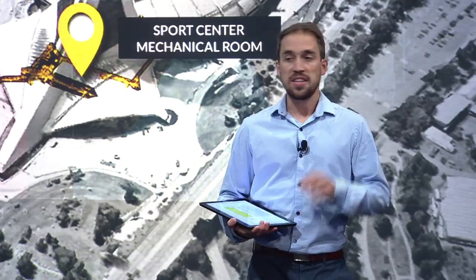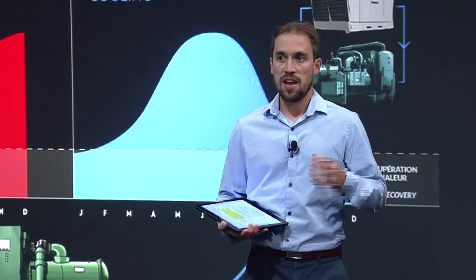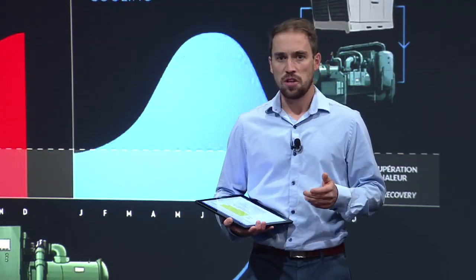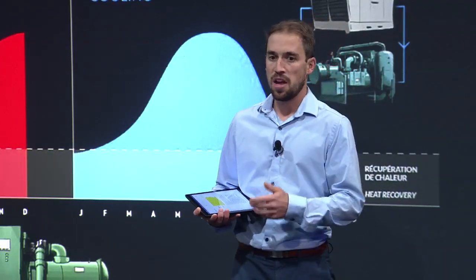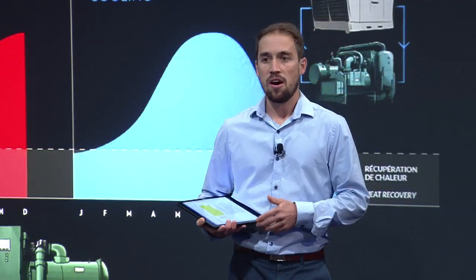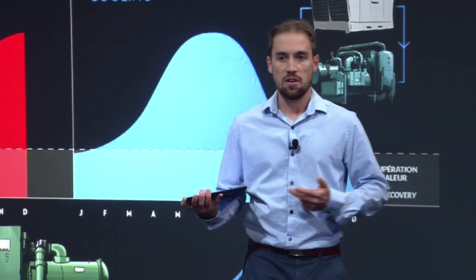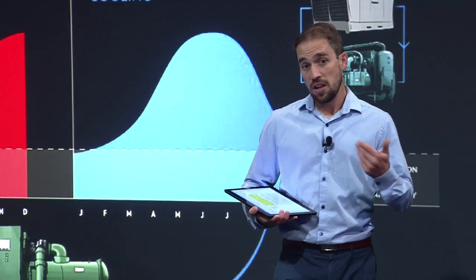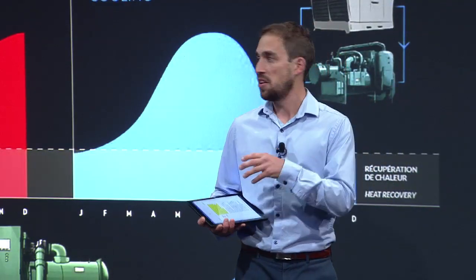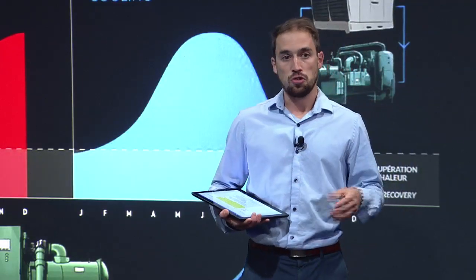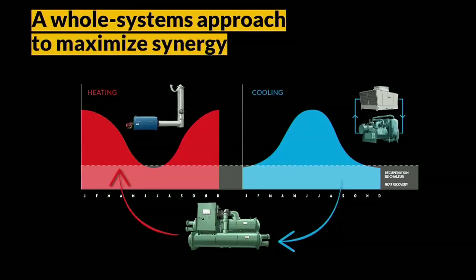Heat recovery is always a key measure in a project, because it's one of the measures that adds the most savings, but it's also always challenging because there's complex design around it, and sometimes new products that are harder to operate, or at least to manage, because there's a lot of interaction between all the systems. At the Olympic Stadium, we went a little further, because we designed the capacity of the heat pump so it can take the overall heating load during summer and all the cooling load during winter, in order to completely shut down the gas boilers during summer and the chiller plant during winter. So we ended up having a lot of operating savings because we were able to reduce the surveillance of the stationary engine in the boiler plant and chiller plant.